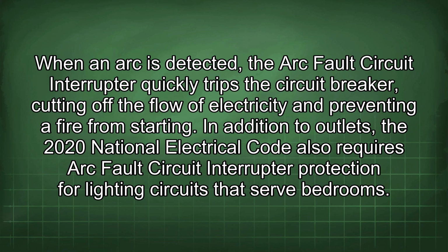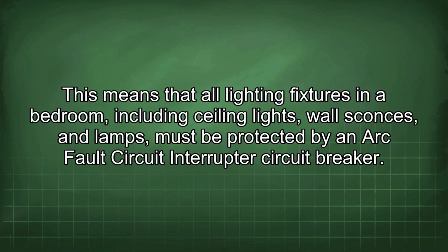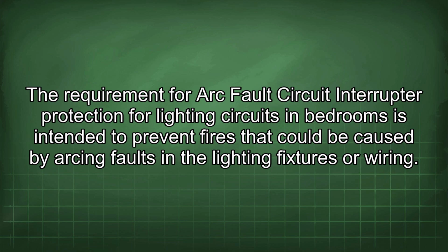In addition to outlets, the 2020 National Electrical Code also requires arc fault circuit interrupter protection for lighting circuits that serve bedrooms. This means that all lighting fixtures in a bedroom, including ceiling lights, wall sconces, and lamps, must be protected by an arc fault circuit interrupter circuit breaker. The requirement is intended to prevent fires that could be caused by arcing faults in the lighting fixtures or wiring.